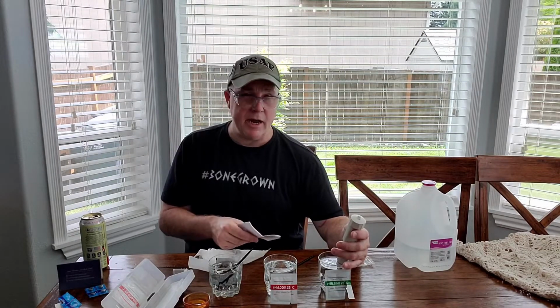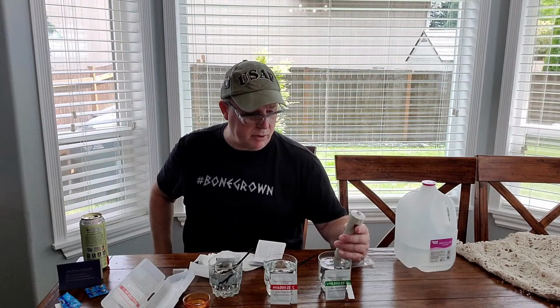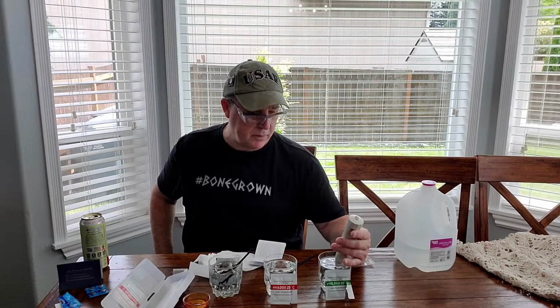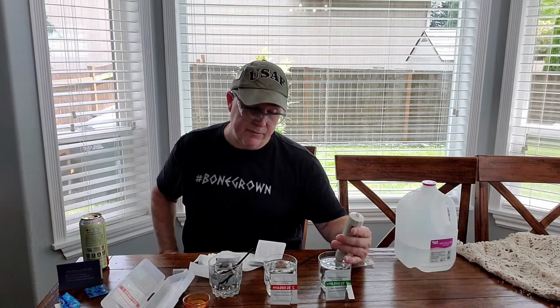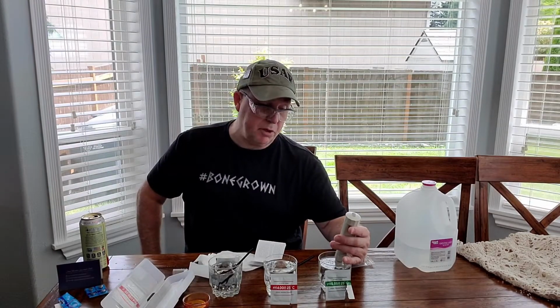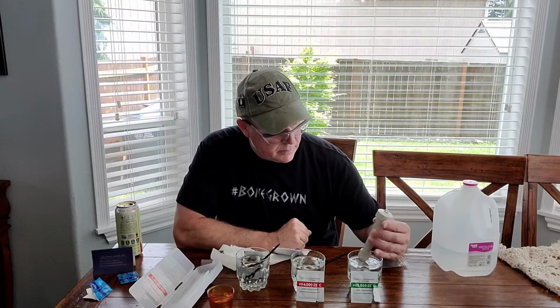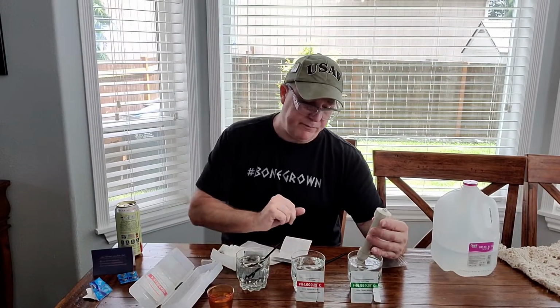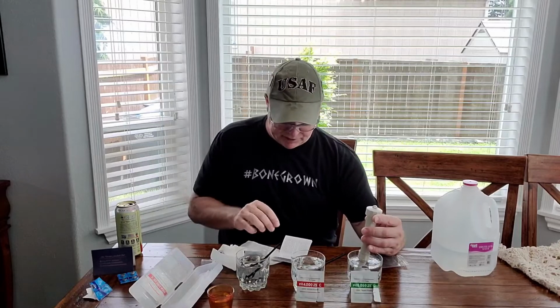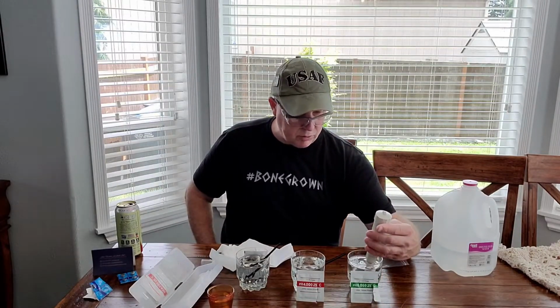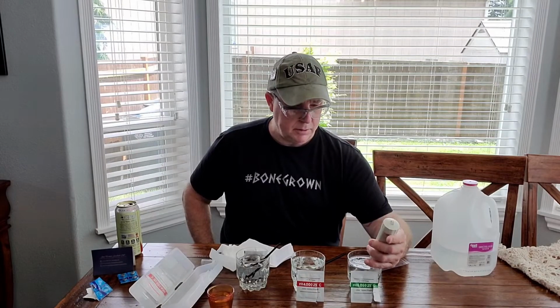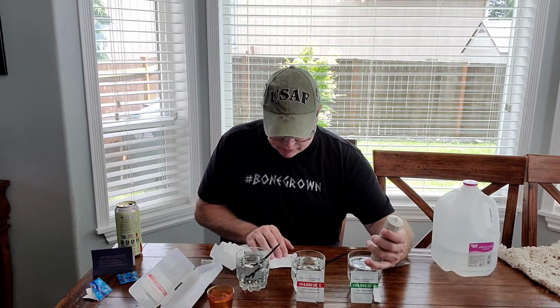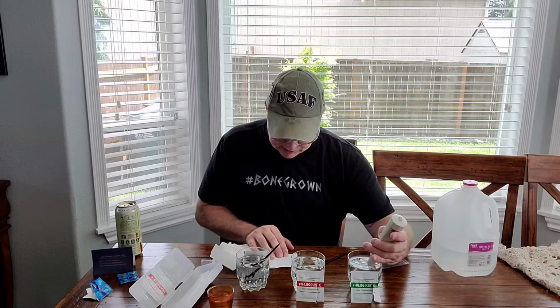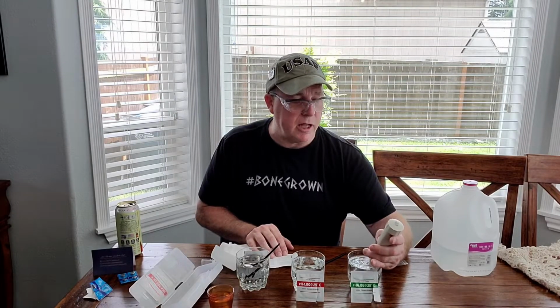So I'm waiting now. What I'm waiting for now is my gauge to stabilize on the number. So I'm watching it. And I have the portion down below, it's completely submerged. It's stabilizing at 6.59. Now this solution's already been stabilized, so I know it's correct, and I want to hold it still. And it's locked on at 6.59. Next I'm going to press the calibrate button for 3 seconds. 1, 2, 3. The calibrate comes on.